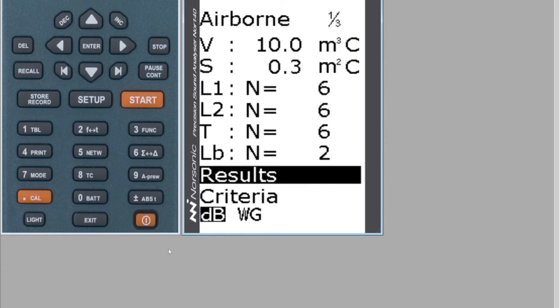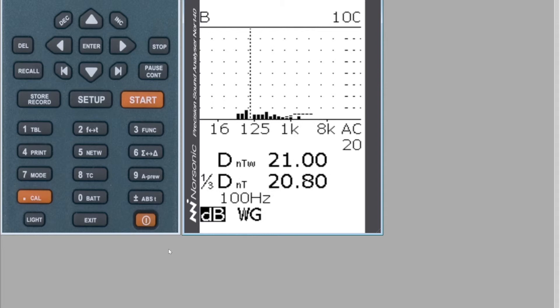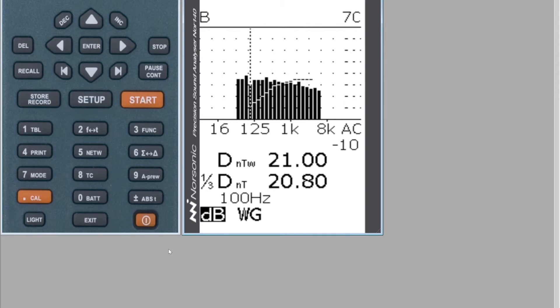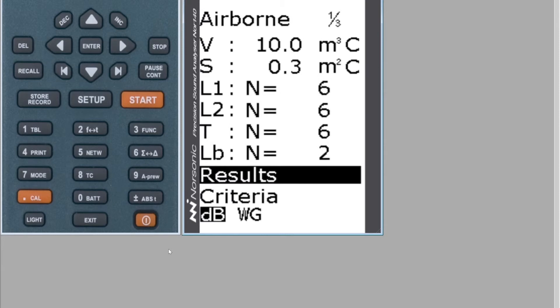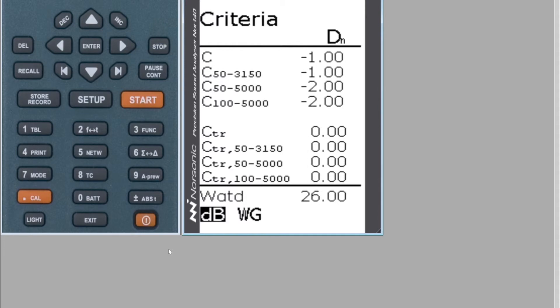To view the results, go down to Results and hit Enter. You'll see the Dw — the difference. If you press the Function key, button number three, then you can switch to DnW and DnT,w. If you press the Inc key, this will pull up the third-octave spectrum and you can see the reference line. To go back a screen, press Enter, go down to Criteria, and you can see the corrections there. Press the Function key to change the function to Dn, Dnt, and so on.